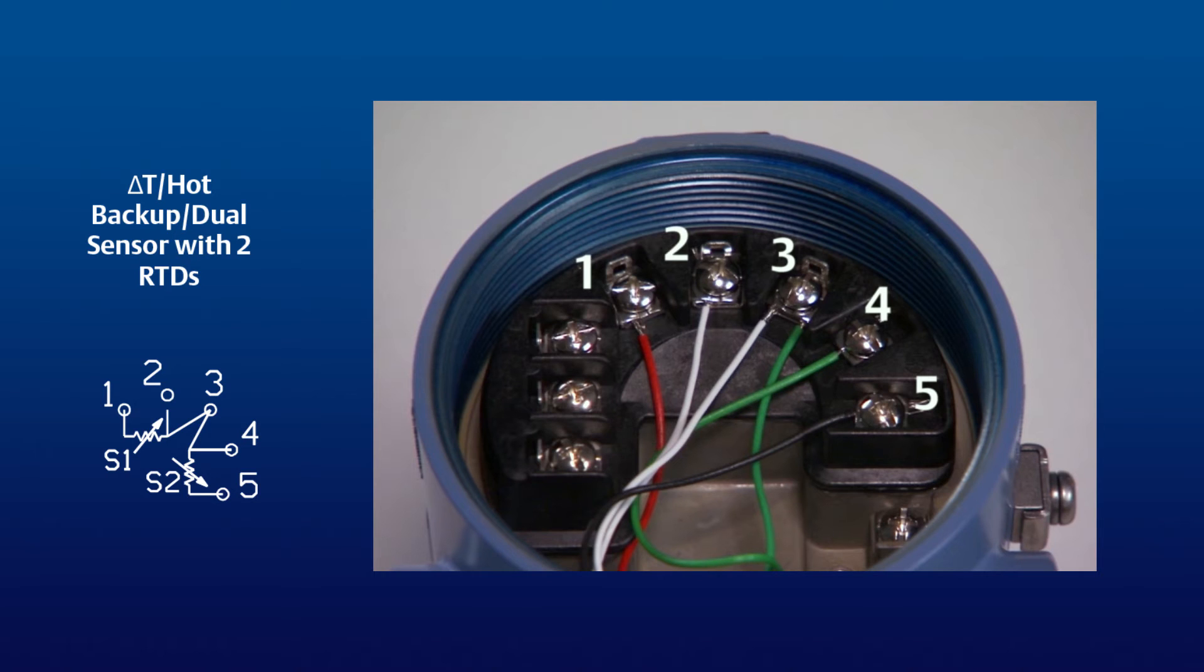Then for the second RTD, the two green wires are connected to terminals 3 and 4, with the single black wire connected to terminal 5. Note that there are two wires attached to terminal 3.